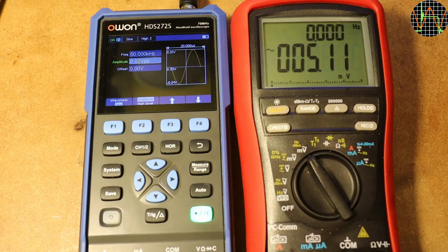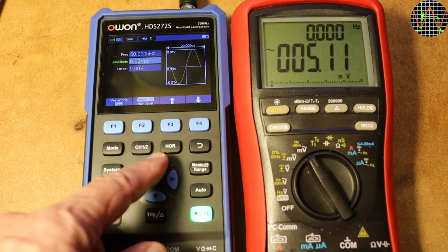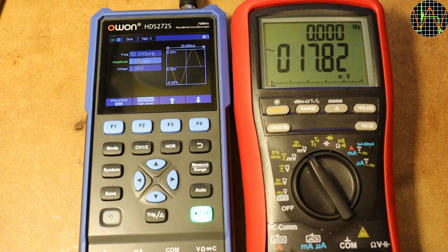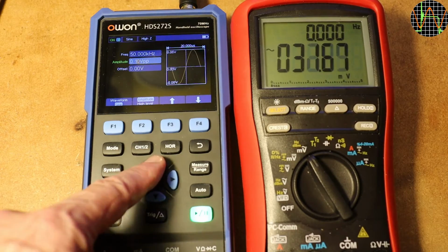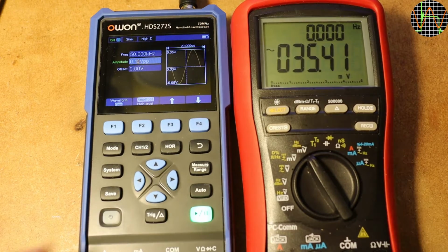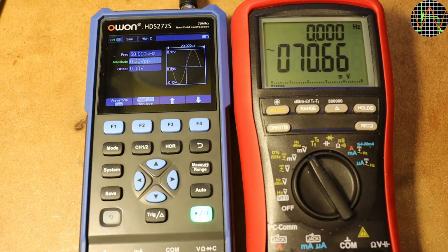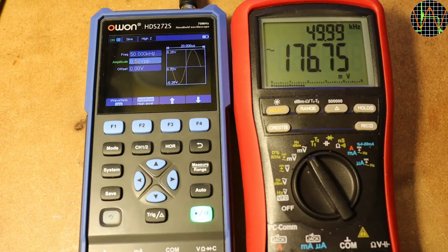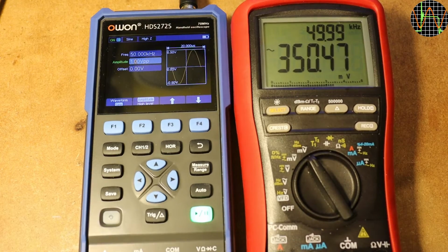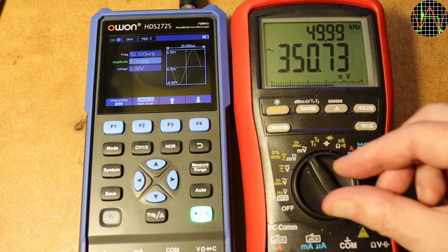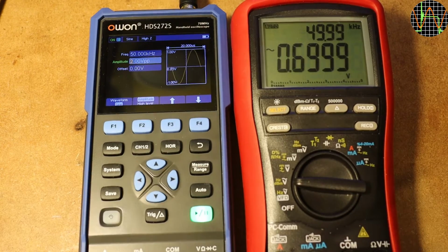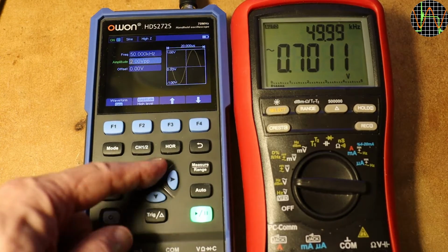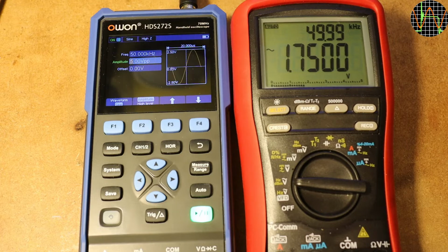Next, I was interested in how accurate the amplitude of the generator is. For this test, I picked 50 kHz, which the BM869S can still comfortably measure, and slowly increased the generator amplitude using the high Z setting. The value on the OWON is volts peak to peak, but the BM869S measures RMS, so one has to divide the VPP value by 2 times square root of 2 to get the equivalent RMS voltage.